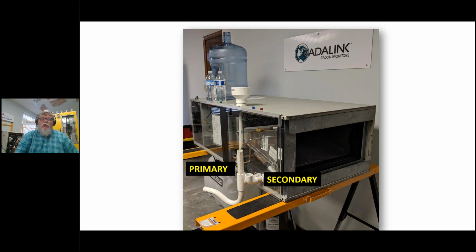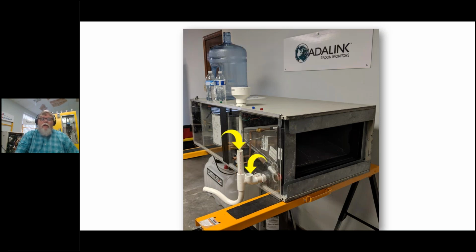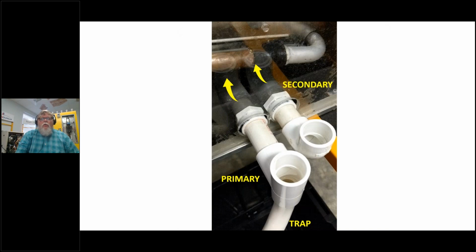And what happens is when the unit's running, that coil's under negative pressure. Air pulling in across the coil's under negative pressure, and I end up with air being pulled in here. You think, well, is that going to stop it from draining? It almost always does. I mean, there could be a duct system in such a way that it may not, but it is so rare that you've got to trap it, and you've got to make sure that trap is being used properly. Look at this video right here.